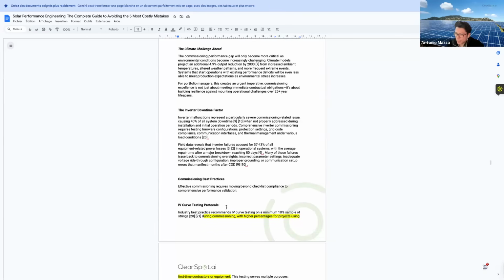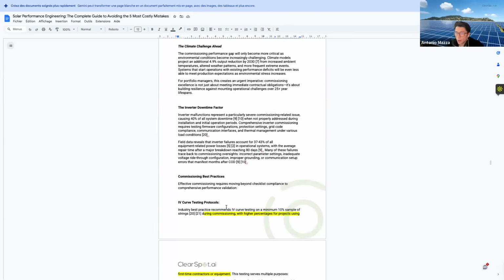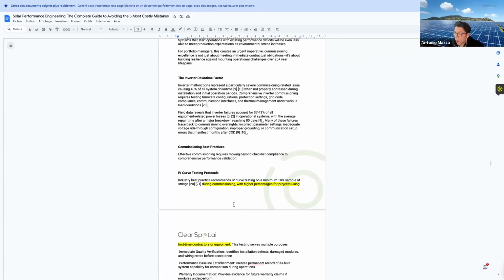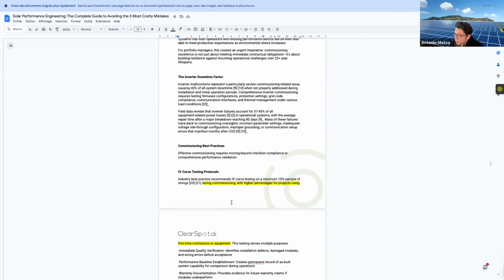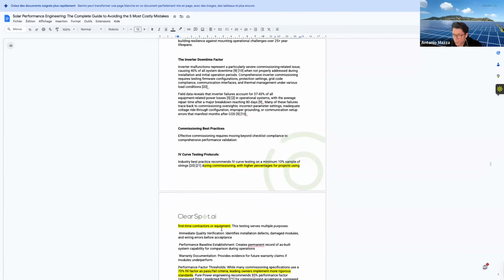What are the commissioning best practices? If you're listening, if you're in charge of that, take notes. IV curve testing protocols: IV curve, maybe not all of you are using it or practicing it. But it's one of the industry best practices, recommended in order to test a minimum of 10% sample of strings during commissioning, particularly for projects using first-time contractors or equipment. What is the purpose? Immediate quality verification, performance baseline establishment, warranty documentation. Guys, warranty documentation. Manufacturers will not give you your money back without documentation, normally, you know that. It provides evidence for future warranty claims if modules underperform.